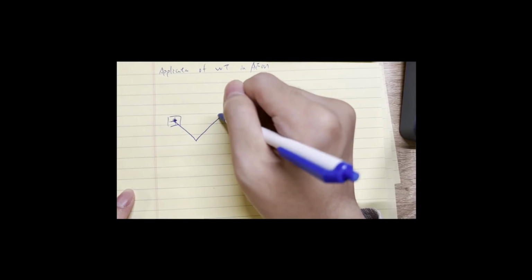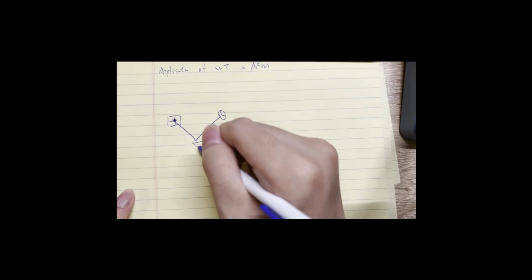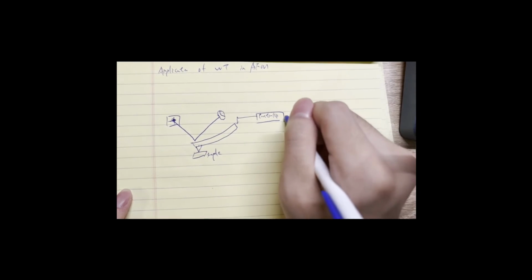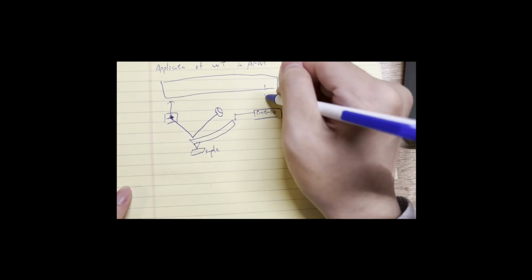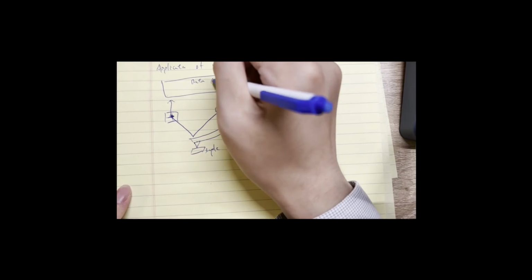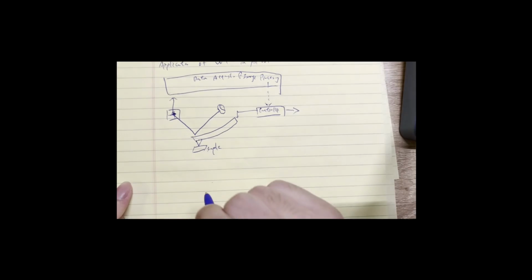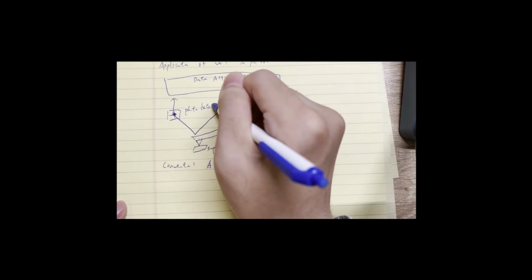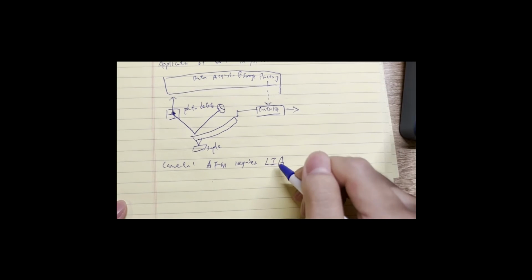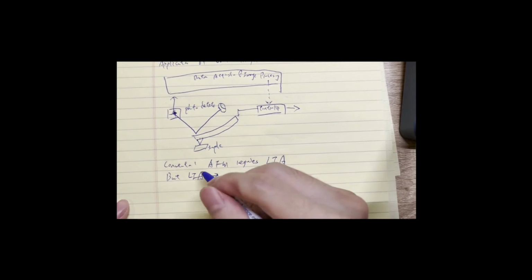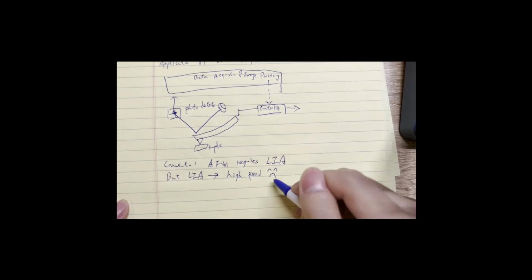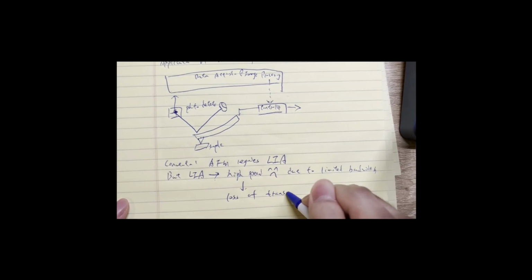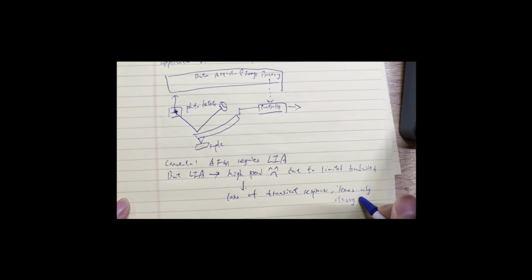Here we have basically an AFM model which consists of a photodiode, a laser, and a cantilever. And we have the sample here, and we have the control loops. Inside the control loops, we need to do the data acquisition and the image processing. So what's the problem? The problem is that conventional AFMs usually require lock-in amplifiers. And these lock-in amplifiers have a finite bandwidth, and this makes them not ideal for high-speed application scenarios because they lose some of the transient response and only catch the steady state response well.